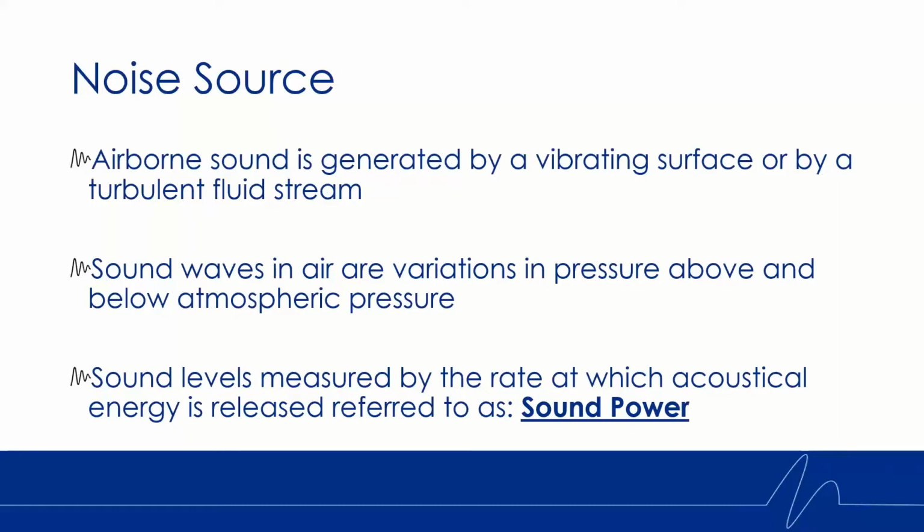The rate at which these sound waves or acoustic energy is emitted from the sound source is called the sound power. This is the rate at which acoustic energy is released from a source. It's a fundamental property of that piece of equipment, so it has nothing to do with where the receiver is in relation to the sound source. It has nothing to do with any of the environmental factors around the sound source either.